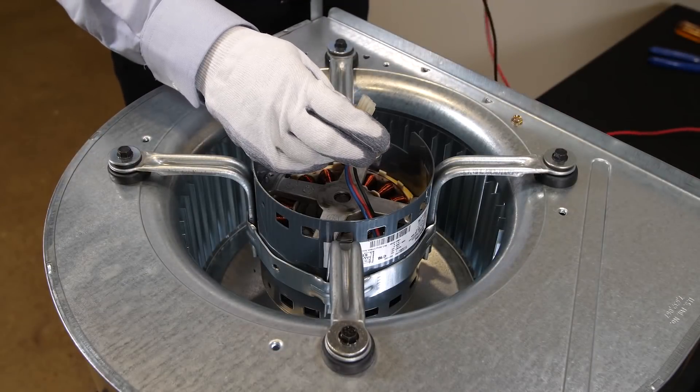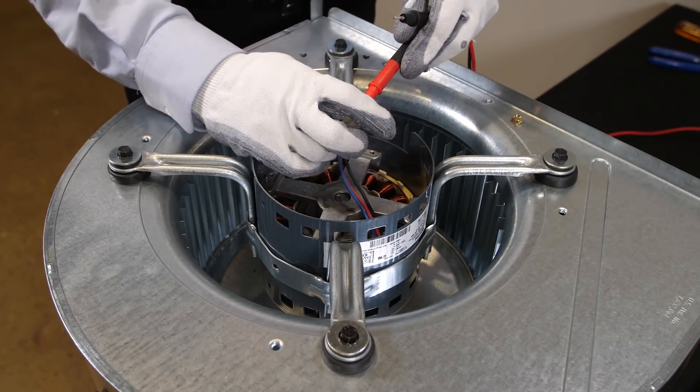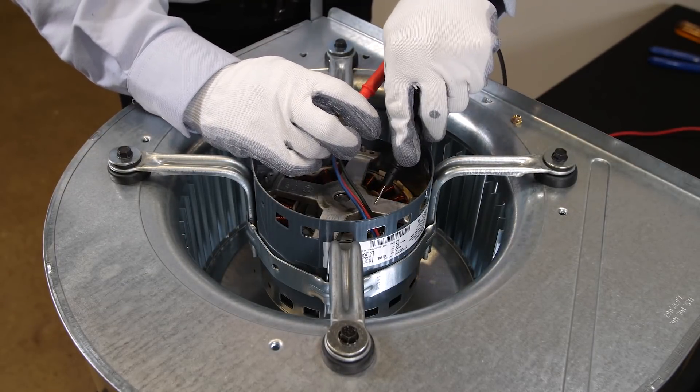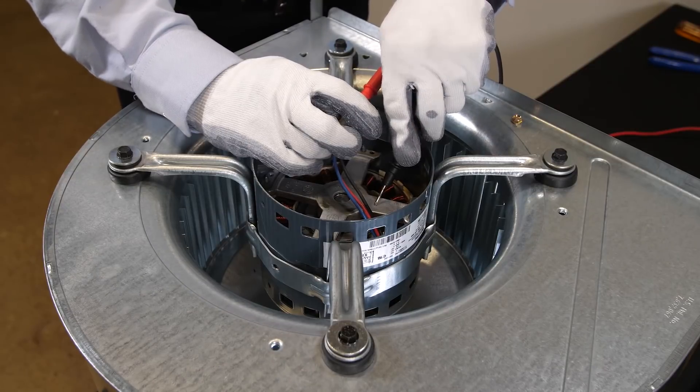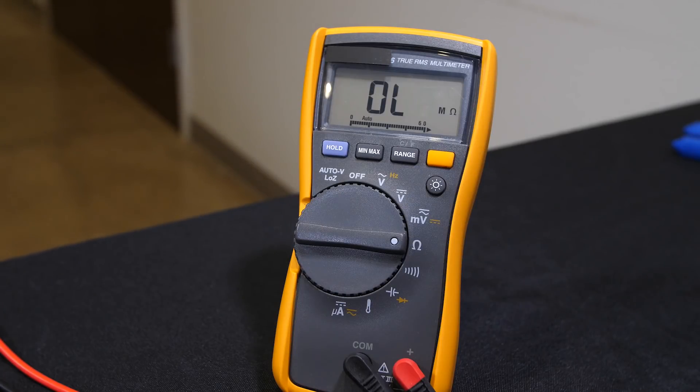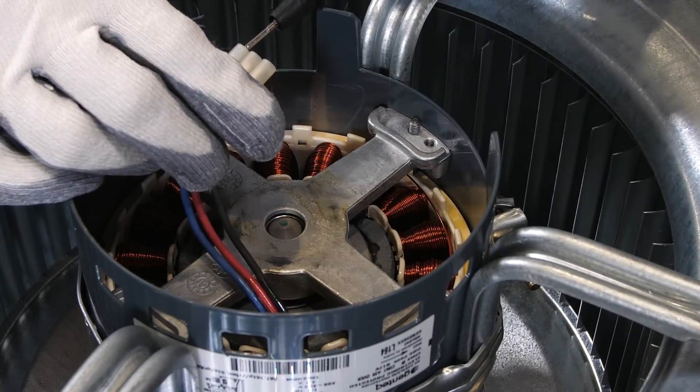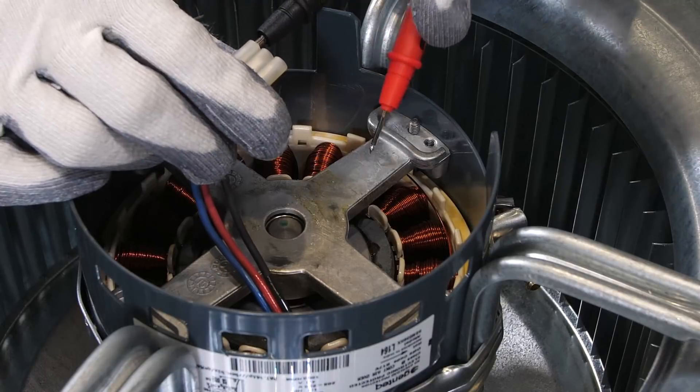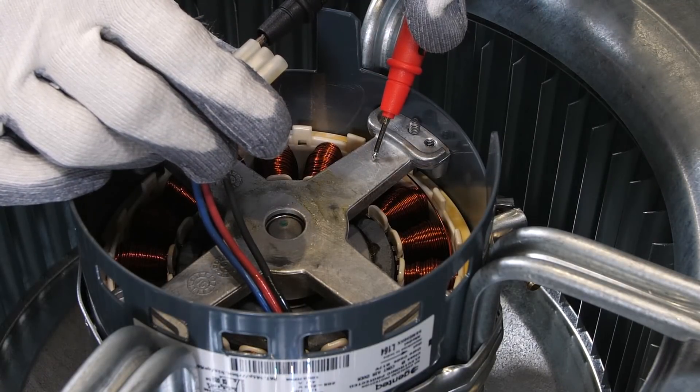Check for short to ground. Use an ohmmeter to measure the resistance from all three of the motor connector pins to the aluminum end plate of the motor. This resistance should be greater than 100,000 ohms. If this test fails and you have less than 100,000 ohms, you have a defective motor and it needs to be replaced.